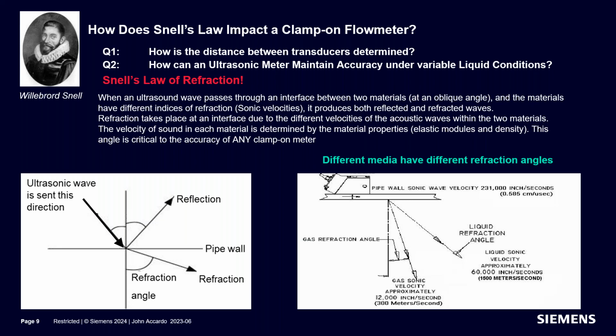A benefit of having a wide beam is that even if you're not perfectly positioned, you still have plenty of energy surrounding the transducers, and the meter is able to find the receive signal and measure the correct speed of sound and know what the refraction angle is. So the wide beam is critical to being able to operate when the speed of sound is changing, so that you do not lose the receive signal at any time.